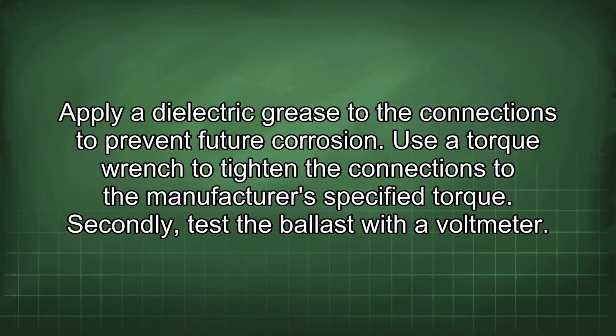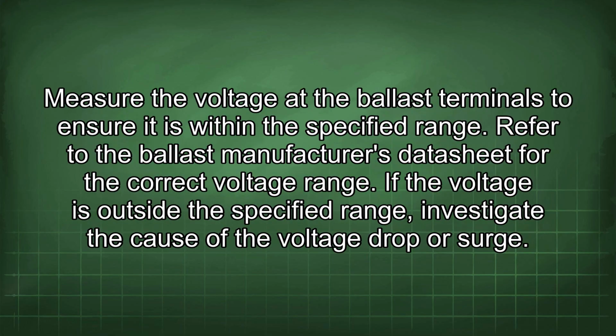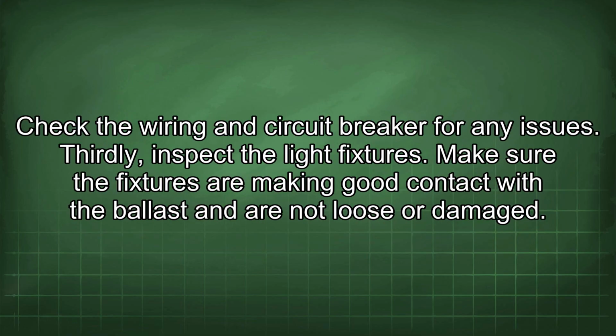Secondly, test the ballast with a voltmeter. Measure the voltage at the ballast terminals to ensure it is within the specified range. Refer to the ballast manufacturer's datasheet for the correct voltage range. If the voltage is outside the specified range, investigate the cause of the voltage drop or surge. Check the wiring and circuit breaker for any issues.